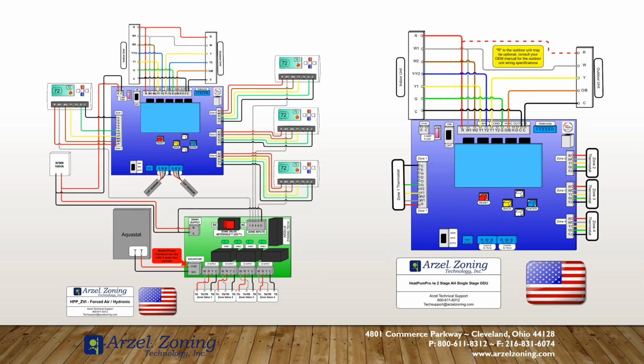So now with your thermostats, if you have hot water heat, your floor heat, W1 from your thermostats brings on the floor heat. W2 from your thermostats, because your thermostat says I need additional heat in this zone, would then bring on the forced air system for that specific zone. And this is a melding of the best of two worlds, because hydronic heat is not good for stat setback.